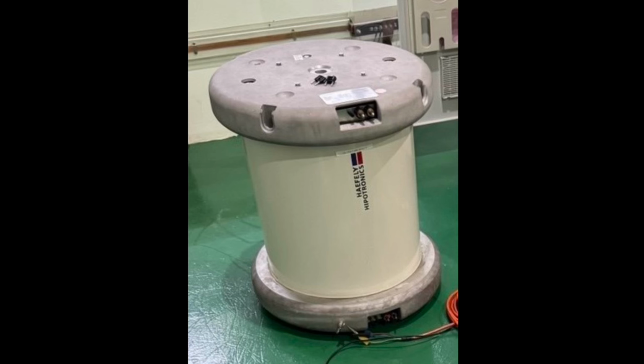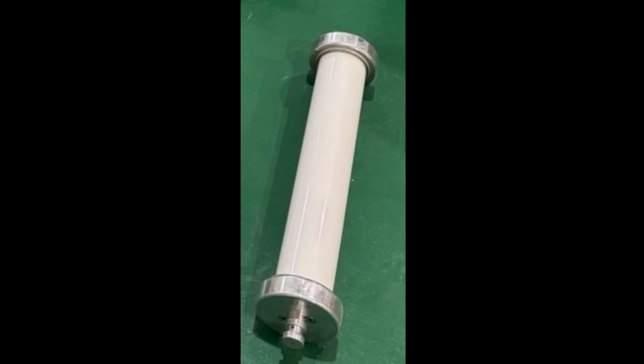The test transformer can be used for AC voltage generation and as a high voltage supply for DC and impulse voltage configuration. This transformer can be set up to 100 kV. This component is the measuring capacitor, which has a capacitance value of 100 picofarad. It can support up to 19.3 kV.